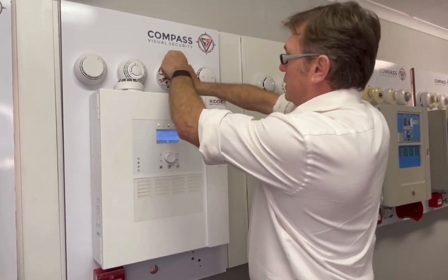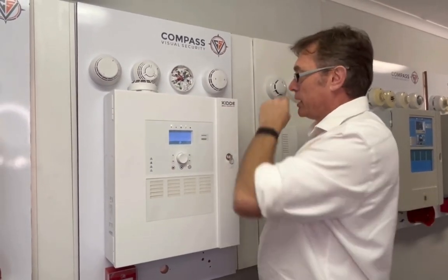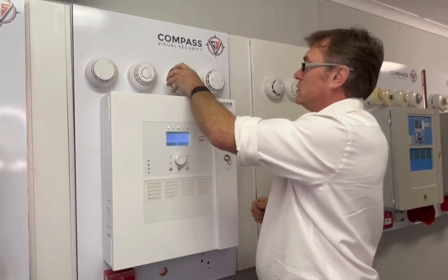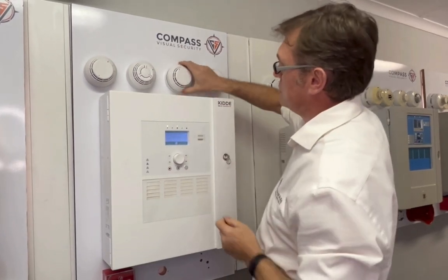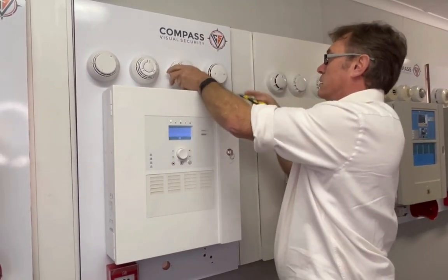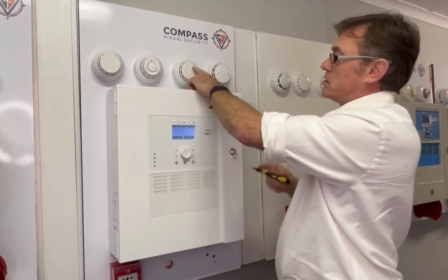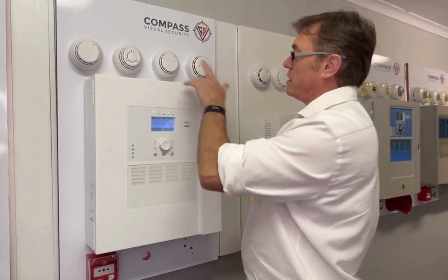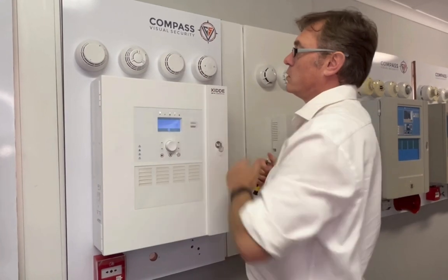So now you can see I've wired my connector correctly, and the detectors have gone back to normal. So when I plug this one back in, we should see a green light flash for a second. Find the right spot. There we go, it's gone green, and it's quite a good indication that there's power there. And then you'll notice every 10 seconds or so I've got the flash LED healthy, so all those devices will flash green.